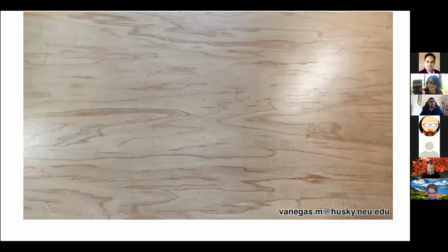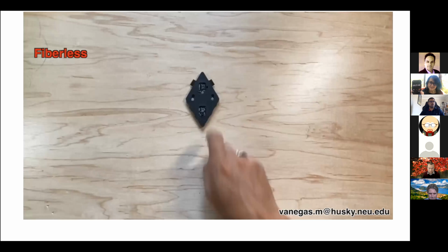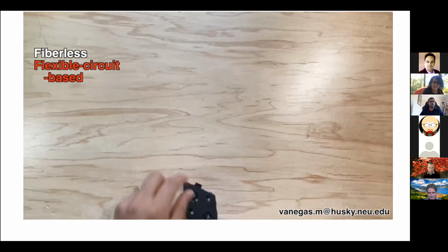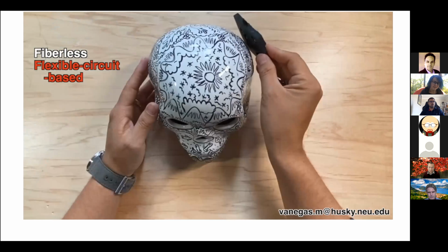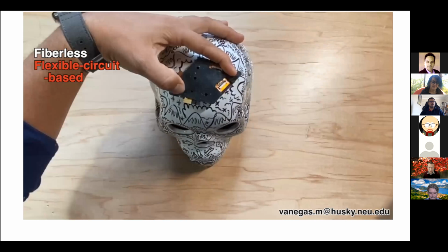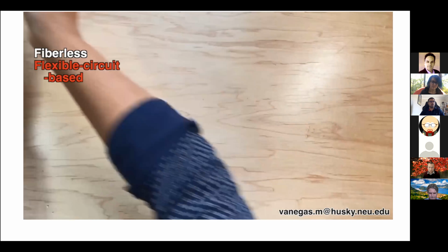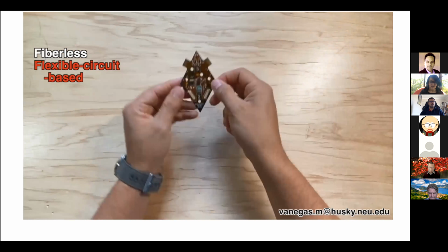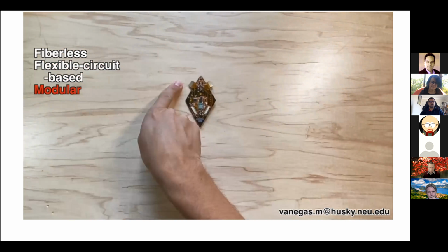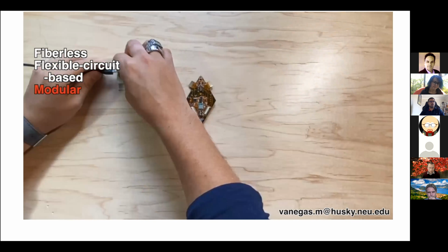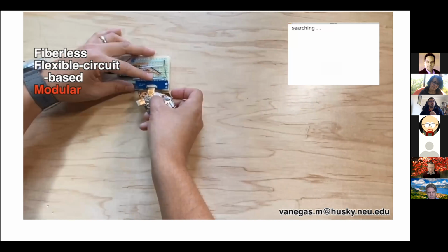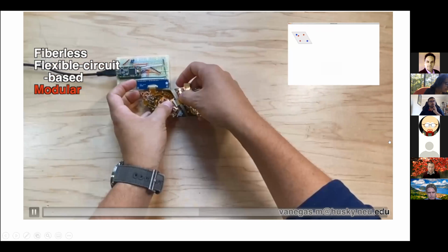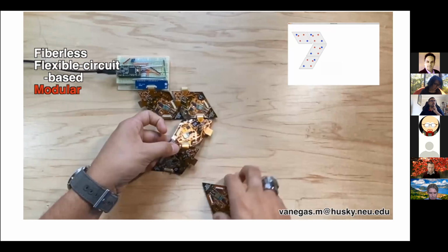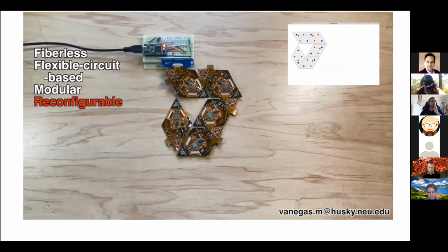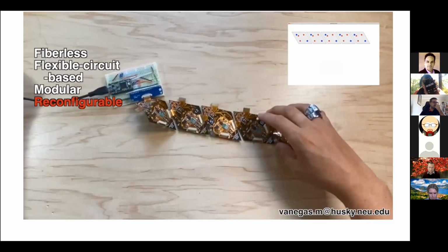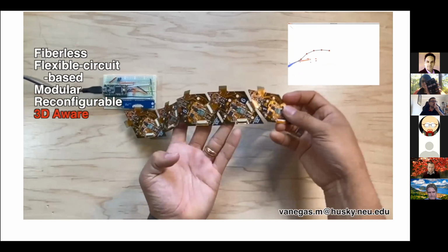So basically, this is the module with a silicone casing, and you can bend it, and you can put it on the surface of a hat, conforming to the contour. And we have some hair-picking holes for better positioning and contact. So basically, the module can be driven by a master node, and then these modules can be interconnected and automatically recognize and reconfigure. You can see the optodes. You can change the position, etc. And a good thing is it has the IMU on the board, so you can see the three-dimensional shape.